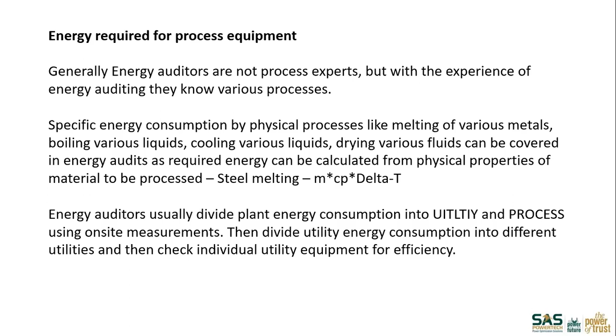Again, dividing and pie charting should lead you fundamentally to approaching significant use, or making a hierarchy. What is the most significant use? What is next to that? And then attack accordingly, so that you come across a bigger chunk at an earlier time, and the client will develop confidence in you. Otherwise, if this approach is not followed, people go on the first day, and their reports will talk more about replacing conventional lighting by LEDs, and they might skip a few obvious things like pumps and blowers, where a lot of energy is being wasted. So if one follows some basic hierarchy, you can give good results to clients.